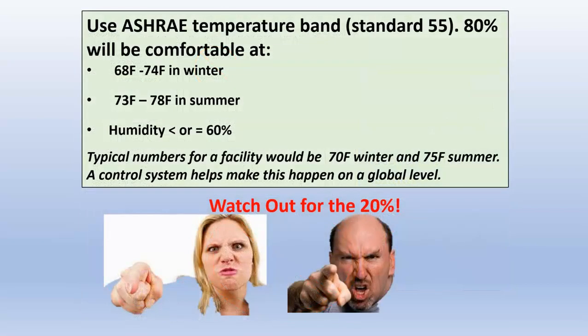All right, another thing, use the ASHRAE temperature band, Standard 55. And what this states is 80% of all occupants will be comfortable at 68 to 74 in the winter, 73 to 78 in the summer, and a humidity less than or equal to 60%. Typical numbers for any facility are 70 winter, 75 summer. And a control system obviously is going to help make this happen. But you see those pictures of those mean-looking people. Unfortunately, there are people like that.